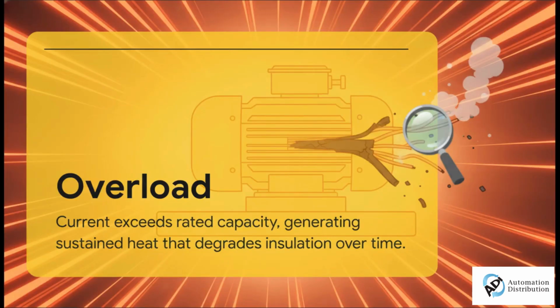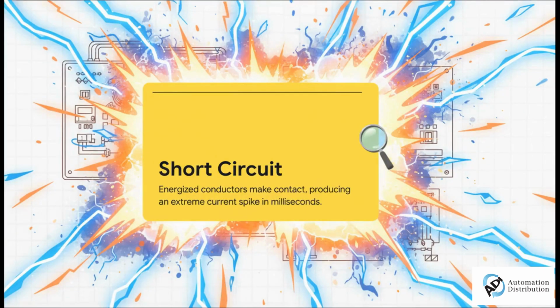First up, we've got the overload. Now, I want you to think of this as a slow burn. It's not some big dramatic explosion. It's more of a sustained overcurrent. Maybe a motor is just working a little too hard for too long. This creates this constant heat that just slowly cooks the wire insulation over time, eventually leading to a failure down the road.